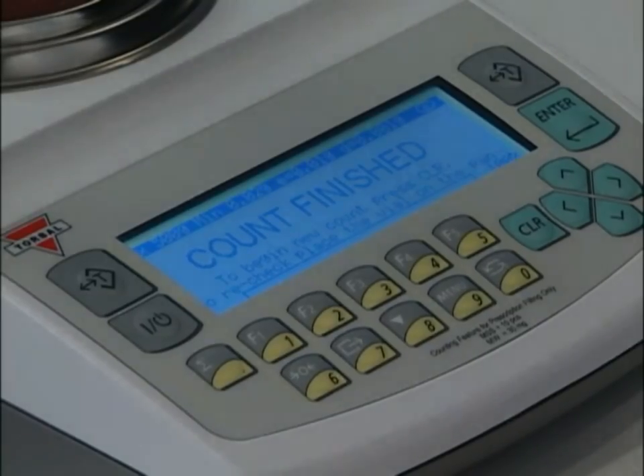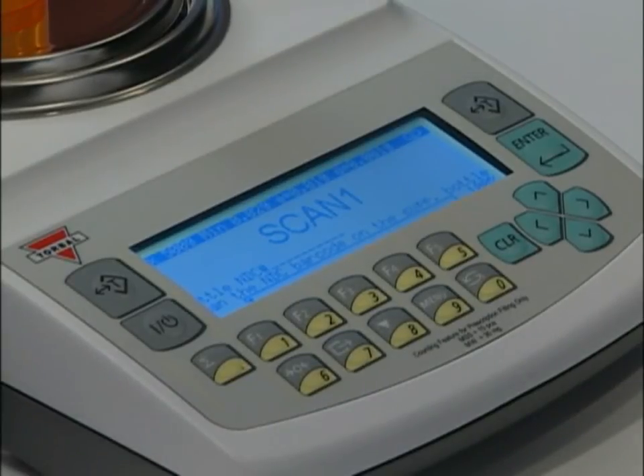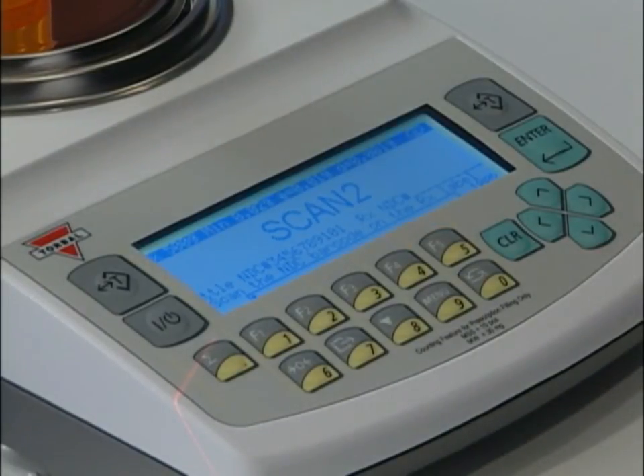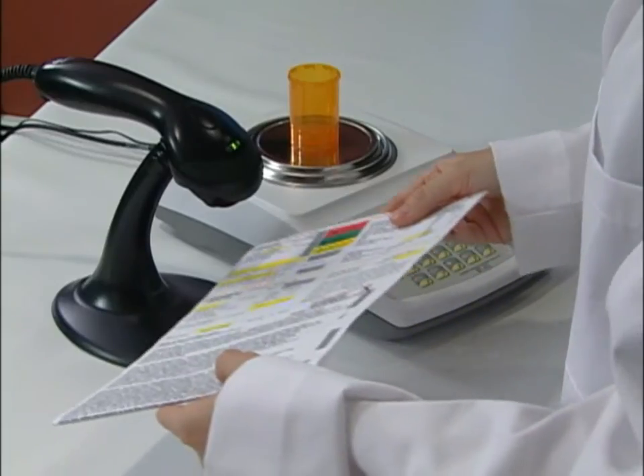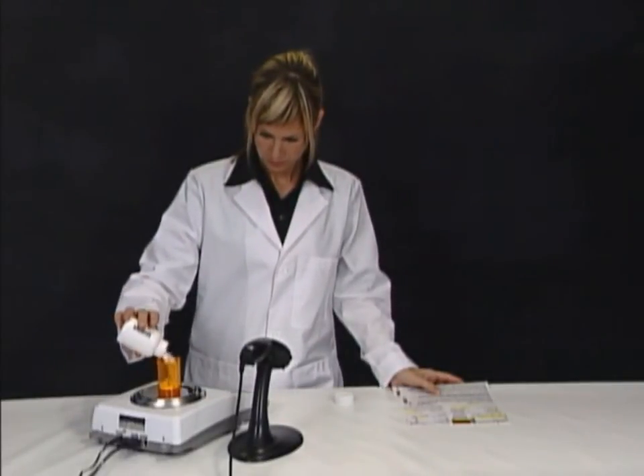Perhaps one of the scale's most valuable features is its ability to verify that the correct drug is counted and filled. When enabled, verification becomes part of the pill counting process. First, tare the vial. The scale will then indicate you should perform scan 1, which is scanning the NDC barcode located on the drug's supply bottle. After you scan the supply bottle, the scale will indicate you should perform scan 2 — scanning the NDC barcode located on the prescription label. After the second scan is performed, the scale checks to see if the codes are the same. If no discrepancy is found, Match OK is displayed and you are allowed to continue with pill counting.